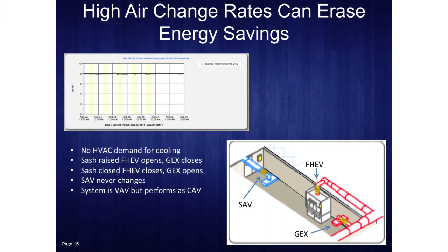This is us trending air change rates in a single fume hood laboratory on our campus, and we expected it to be VAV. We paid for the supply air valve, we paid for the exhaust air valves. We put all this to work, and we tell people to close their sash. Unfortunately, what happens is when you close your sash, your general exhaust valve opens. And when you raise your sash, your general exhaust valve closes and your fume hood exhaust valve opens. And so even though you were doing what was proper, you weren't actually saving any energy. You were just changing the place that the air goes.